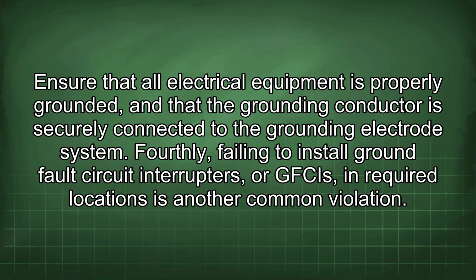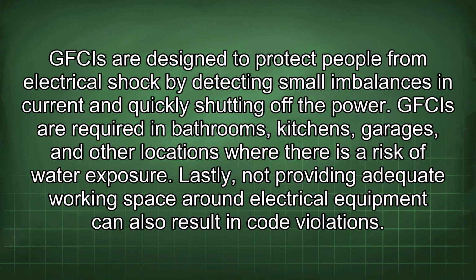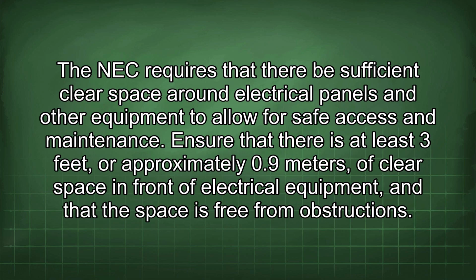the grounding electrode system. Fourthly, failing to install ground fault circuit interrupters, or GFCIs, in required locations is another common violation. GFCIs are designed to protect people from electrical shock by detecting small imbalances in current and quickly shutting off the power. GFCIs are required in bathrooms, kitchens, garages, and other locations where there is a risk of water exposure. Lastly, not providing adequate working space around electrical equipment can also result in code violations. The NEC requires that there be sufficient clear space around electrical panels and other equipment to allow for safe access and maintenance. Ensure that there is at least 3 feet, or approximately 0.9 meters, of clear space in front of electrical equipment, and that the space is free of obstructions.